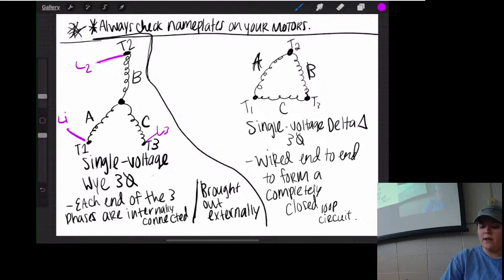In the delta configuration, each winding is wired end to end to form a completely closed loop circuit. At each point where the phases are connected, leads are brought out externally and labeled. The 3-phase line supplying power to the delta motor must have the same voltage and frequency rating as the motor.